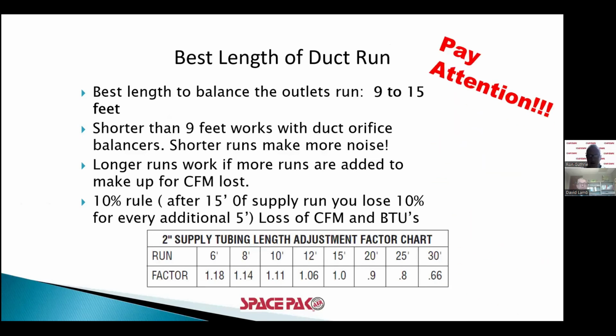This right here is an important slide. This chart is in every installation manual, and basically what it shows, we talk about outlets. A lot of times when somebody's having problems with a system, they'll tell me, well, I got 18 outlets. It's 2.5 ton, I got 18 outlets. Well, the next question is, how long are the 2-inch tubing lengths on those outlets? Because we derate the outlet by the amount of 2-inch tubing that we have on it. So if he's got long runs, he doesn't really have 18 outlets. He's got something less than that.